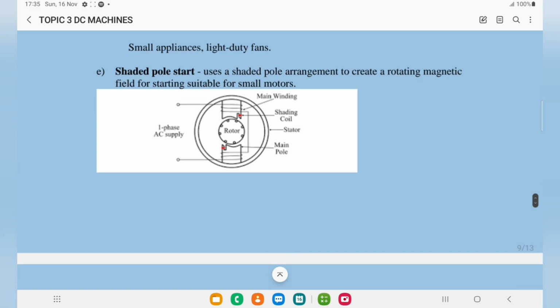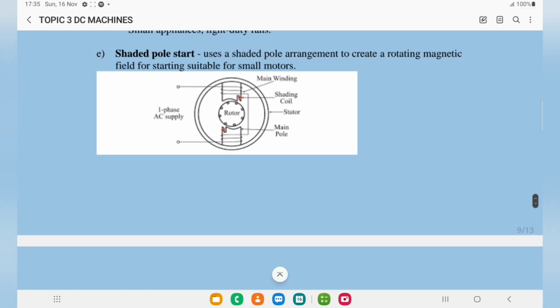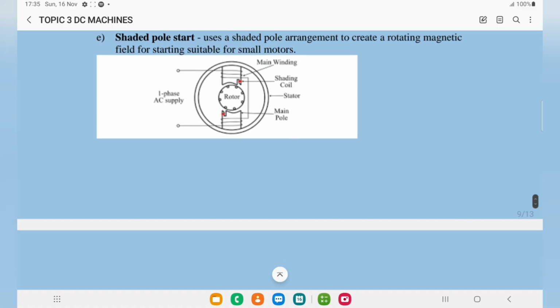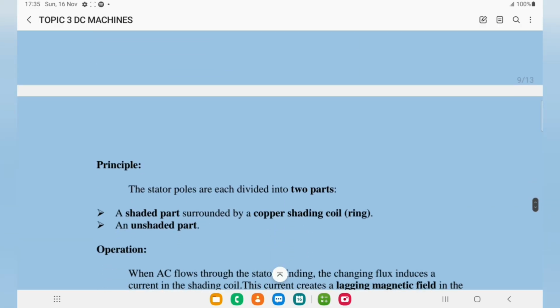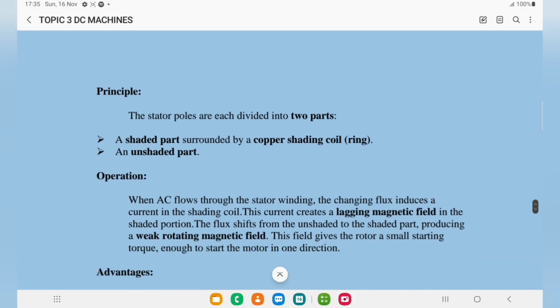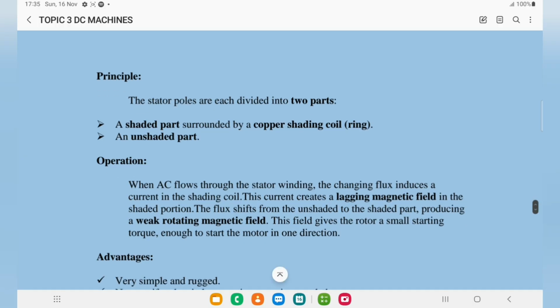Then we have the final single phase motor starting method, which is the shaded pole start. This one uses a shaded pole arrangement to create a rotating magnetic field for starting, and it is suitable for small motors. If you look at how the connection is, we have the main winding, the shading coil, the stator, the main pole, and also the single phase AC supply. When you're talking about the principle of operation, the pole is divided into two parts: the shaded part that is always surrounded by a copper shading ring, and the unshaded part. So when the AC flows through the stator windings, there will be a change in magnetic flux which will induce a current in the shading coil.